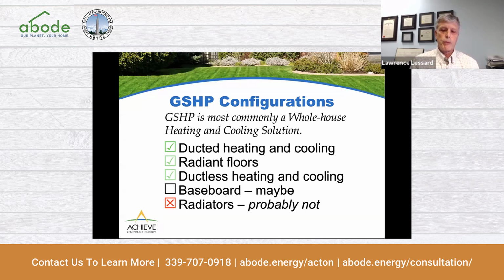That's okay if you've done a bunch of energy improvements to the house and you essentially have more baseboard than you need. But you don't get to do cooling through the baseboard. So ultimately, people will usually pick a ducted or a ductless system because they want the air conditioning, especially in our warming climate. If you have radiators, that's just kind of a no-go as a distribution system. We can't approach the temperatures that are needed for radiators, so something else would be done. But again, even if we could supply radiators, you wouldn't be able to cool that way, so you might be inclined to move to one of the other options.